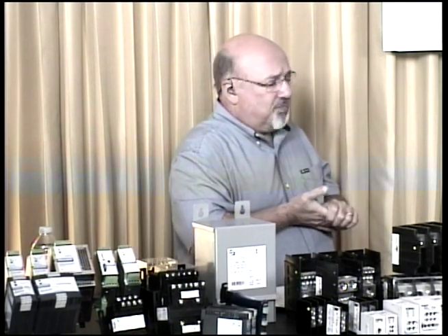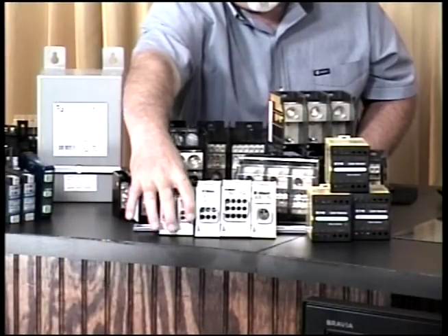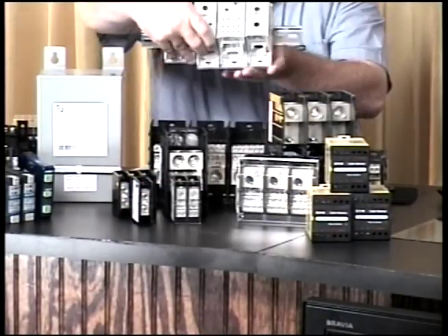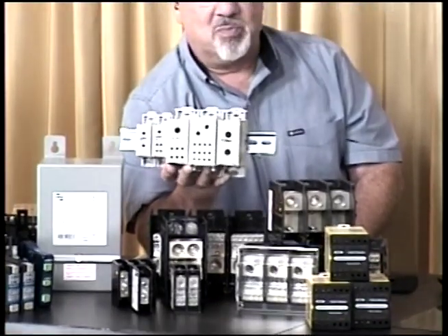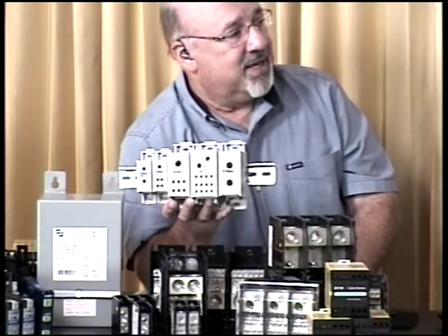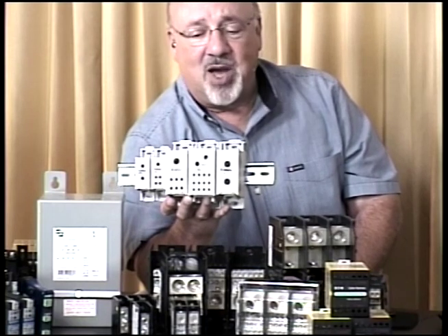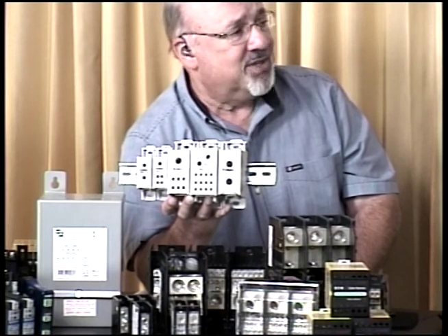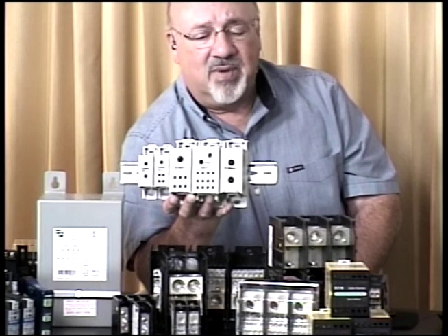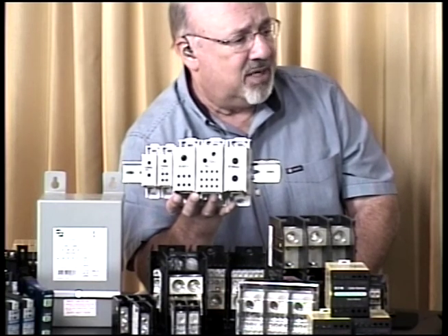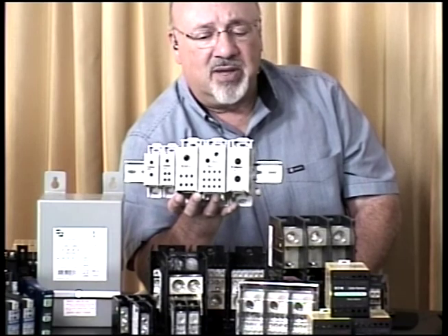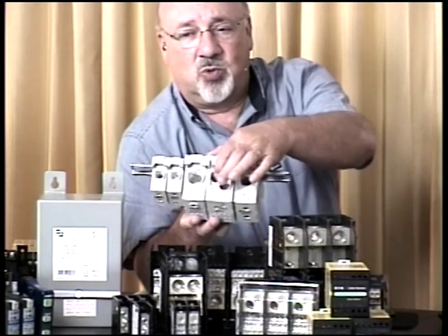And now we get into our power distribution blocks. Basically, there's 2 styles. There's the finger safe operation, which I show here, and these are distribution blocks. Where would you use them? In power distribution, coming into your panel from your 3-phase, after your main disconnect or main breaker, you might need to bring in a heavy gauge wire, which would run into here.